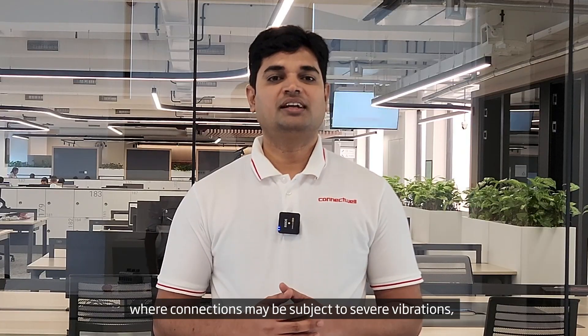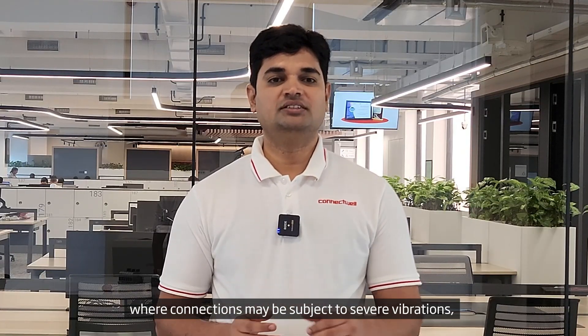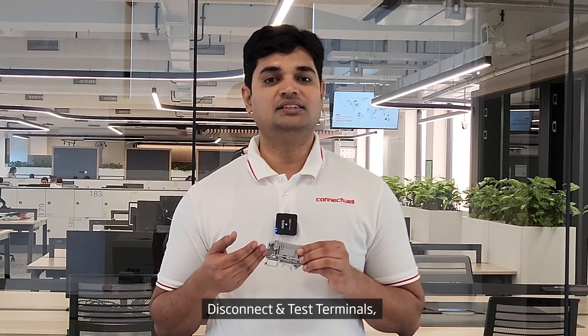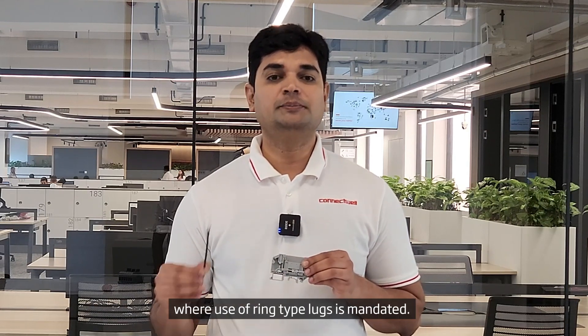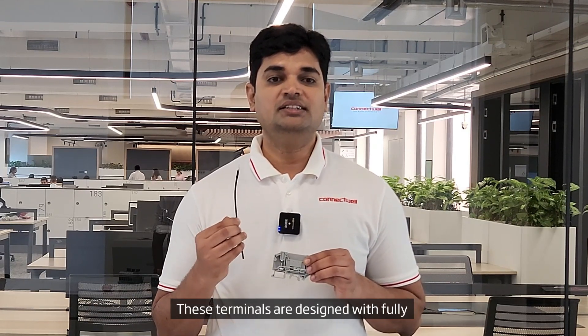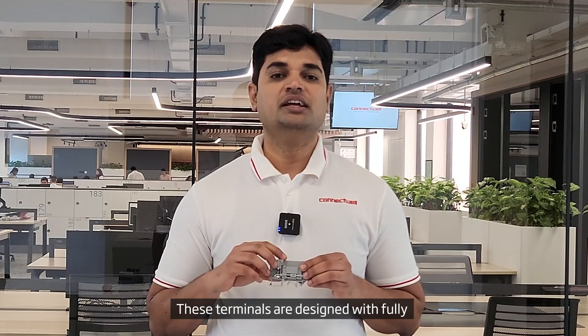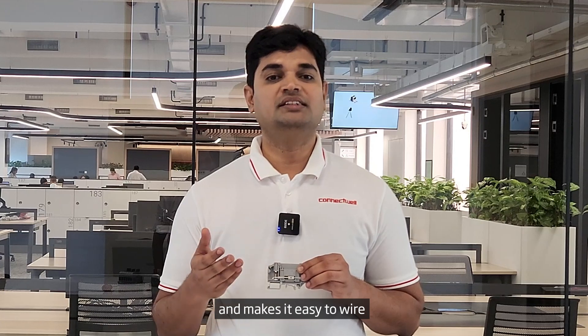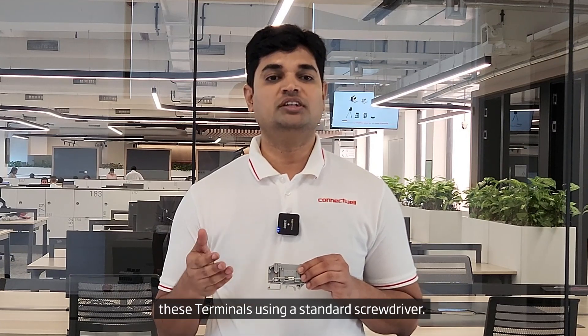For CT circuits where connections may be subject to severe vibration, stud type terminal blocks are preferred. Connectwell offers STH4DT stud type disconnect and test terminals for CTPT applications where use of ring type lugs is mandated. These terminals are designed with fully captive nuts in their shroud, which saves wiring time and makes it easy to wire these terminals using a standard screwdriver.